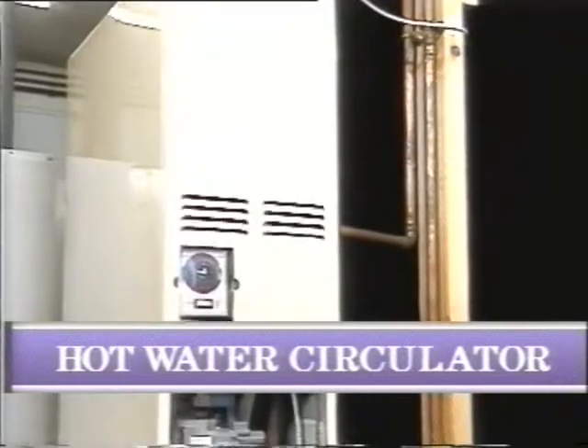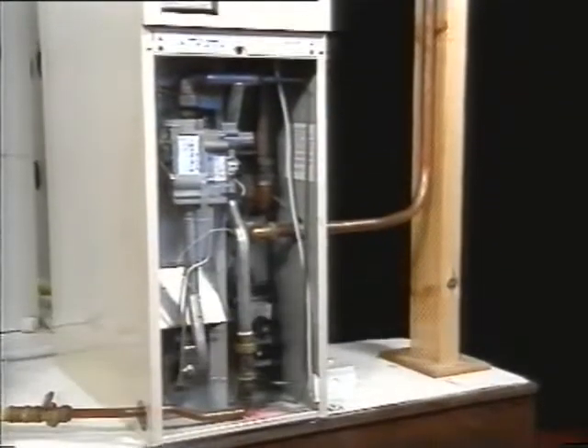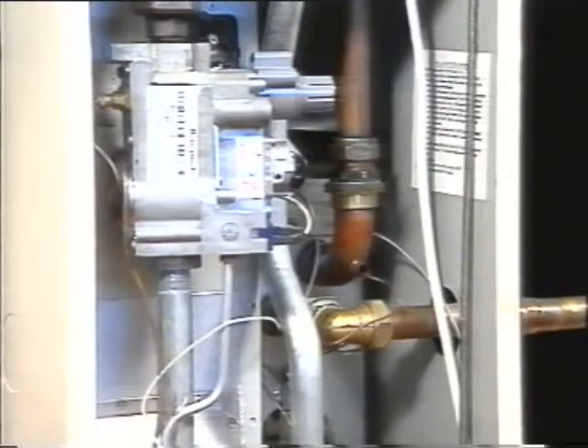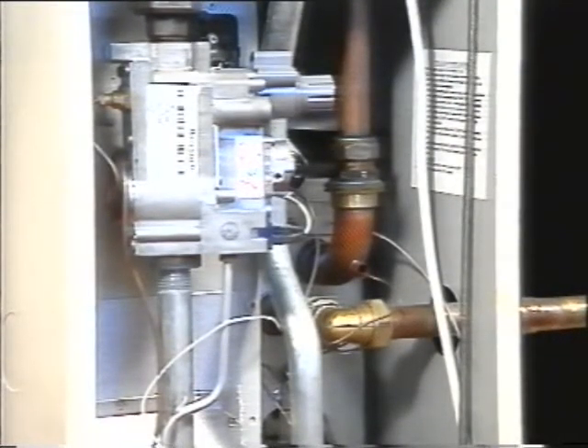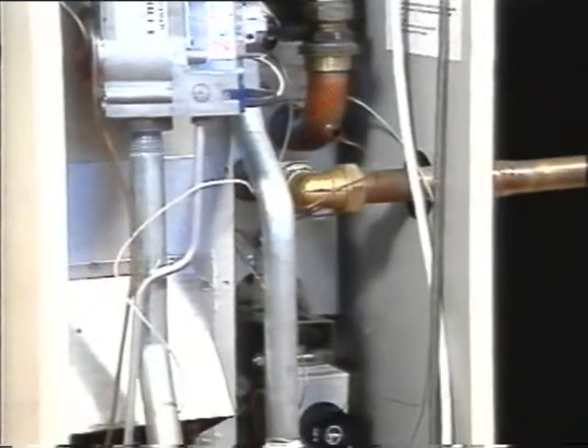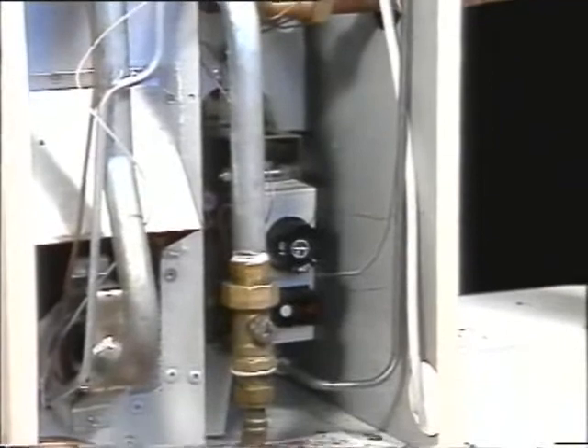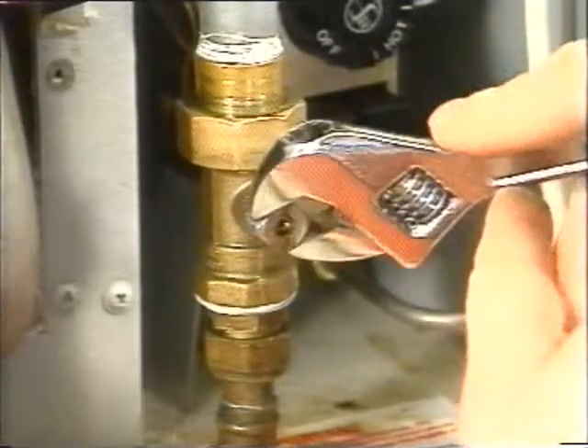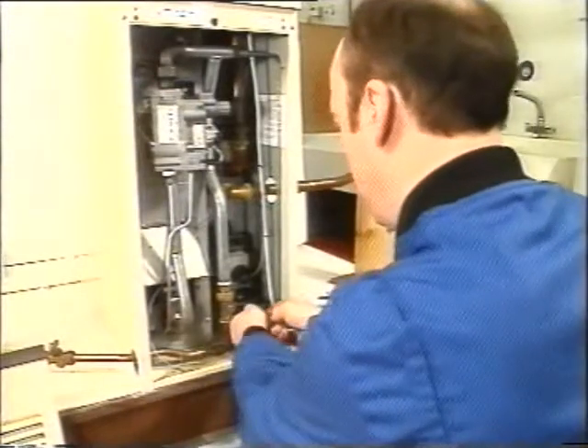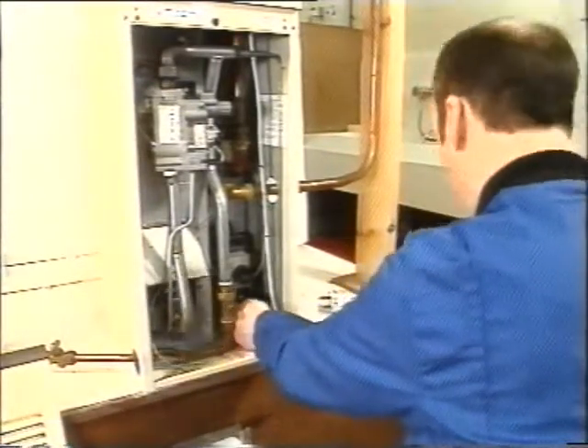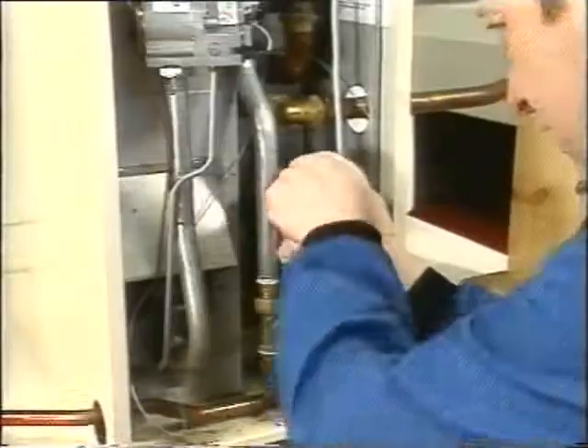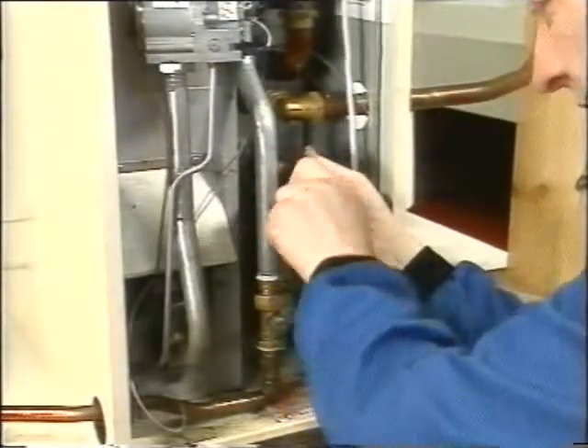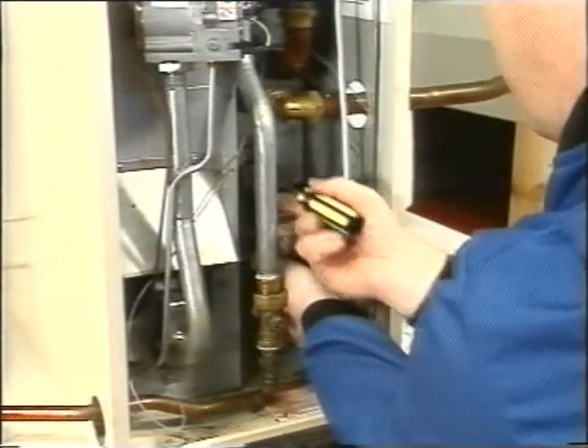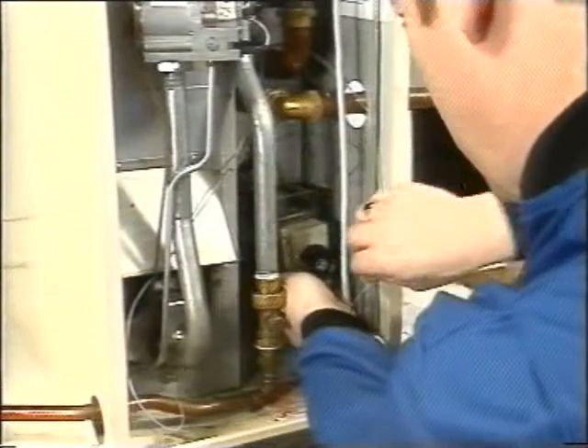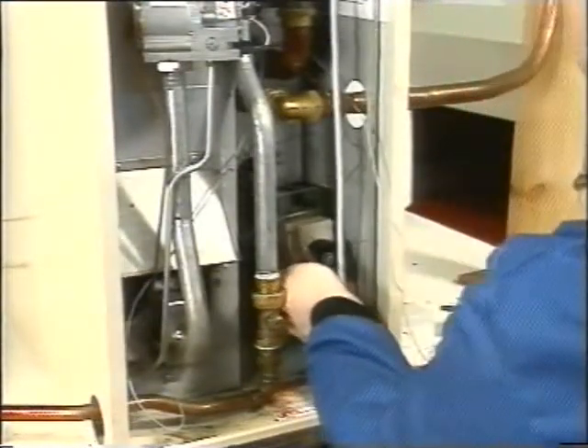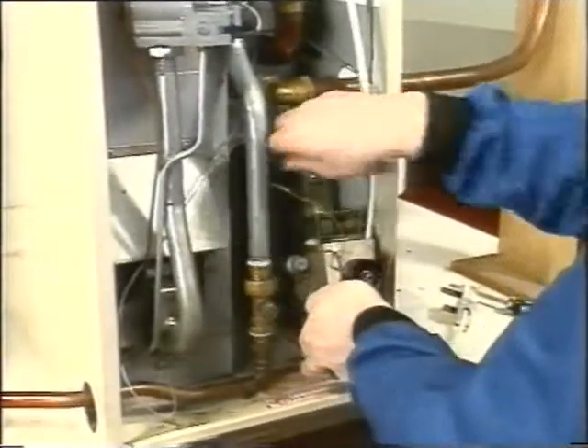A hot water circulator heats storage hot water using gravity flow and return pipes. The water in the storage cylinder can either be heated by a direct or an indirect system, and by one of two types of circulator unit, a back boiler or an independent one. They have similar components, and installation is basically the same, but their locations are very different. Independent units can be installed in a warm air unit compartment or in a cupboard next to the water cylinder. They may be fitted with a multifunctional control unit like this. It houses the appliance's control systems, the gas governor, flame safety device, and thermostat control assembly.